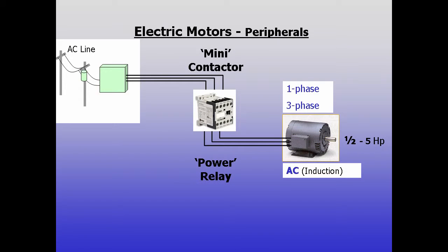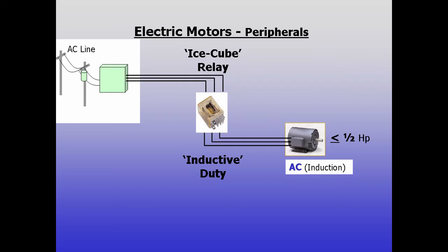Mini contactors, or power relays, can be used with lower horsepower motors. Ice cube relays can be used for motors under about a half horsepower, but they must have an inductive duty rating for the motor size.